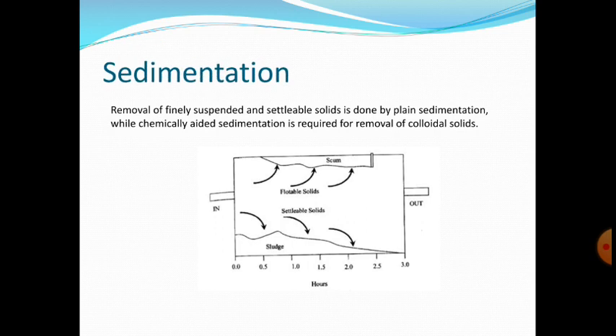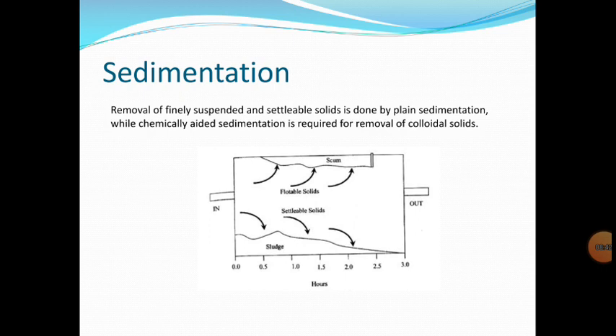The second unit operation is sedimentation. In sedimentation, removal of finely suspended and settleable solids is done by plain sedimentation, while chemically aided sedimentation is required for removal of colloidal solids. Colloidal solids are particles which are very small — soluble or insoluble in liquid — ranging from 1 to 1000 nanometers in diameter. As time passes, the amount of sludge that settles becomes progressively less.